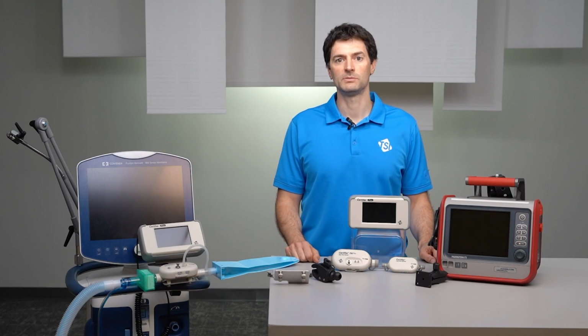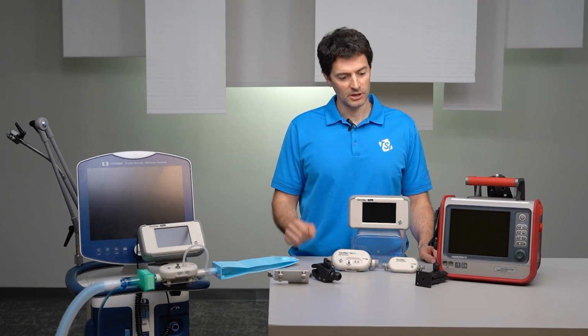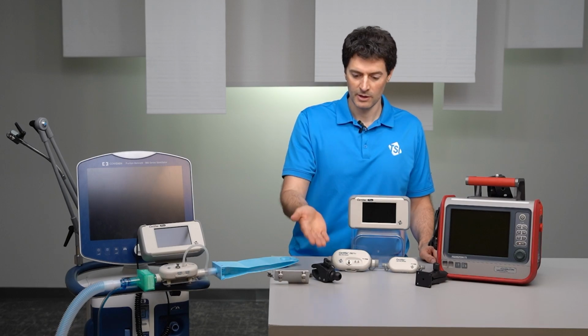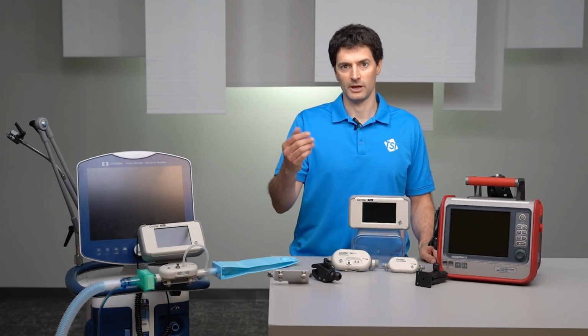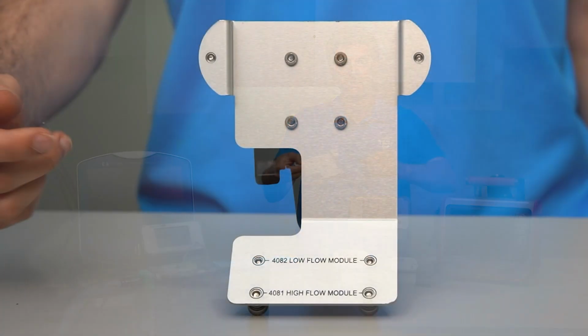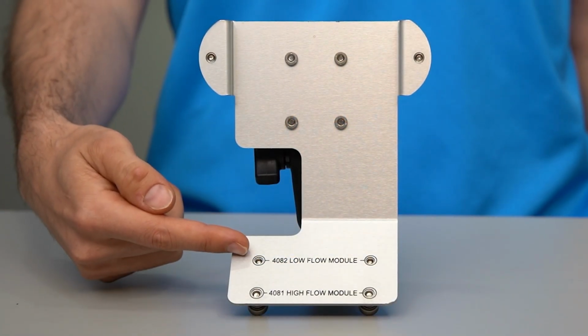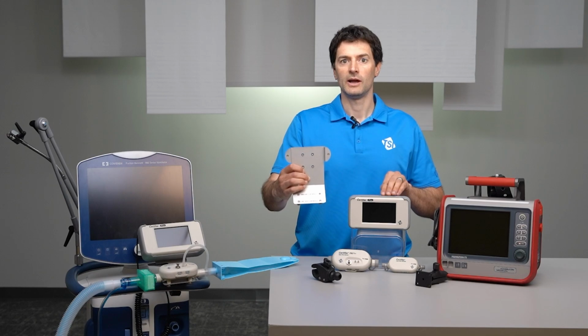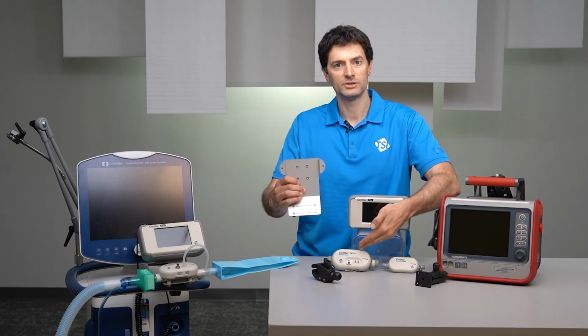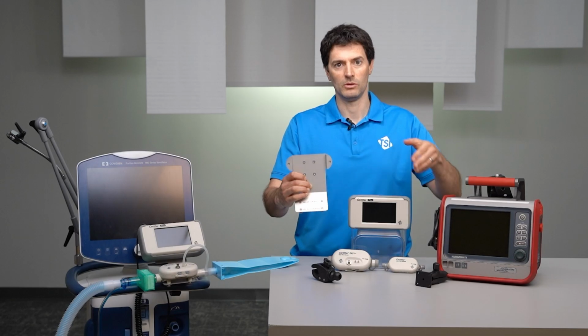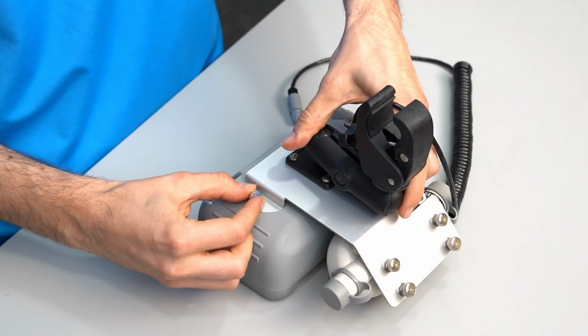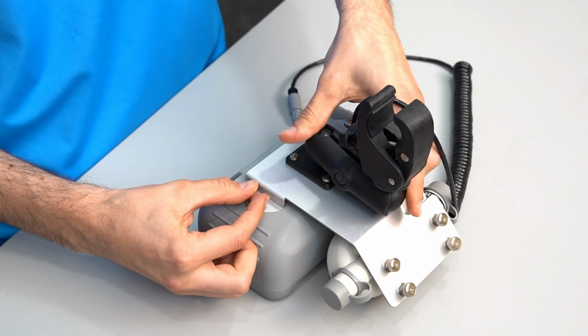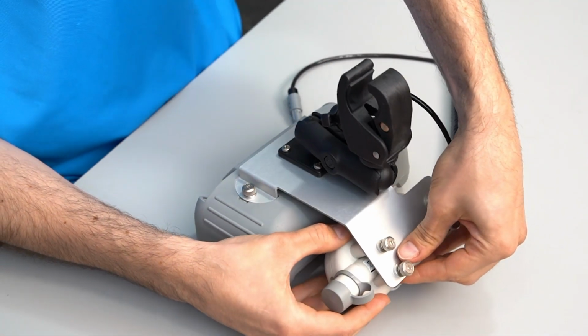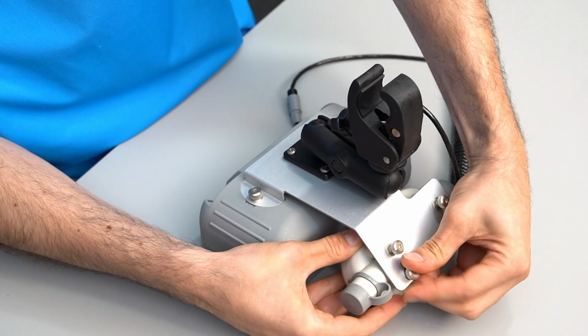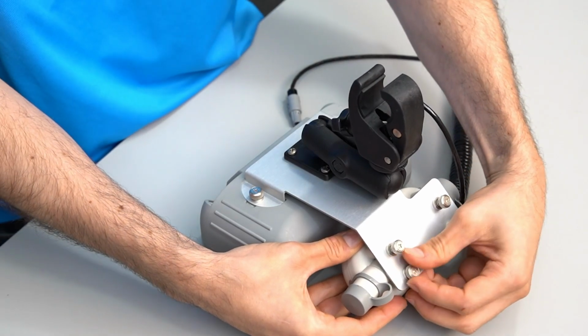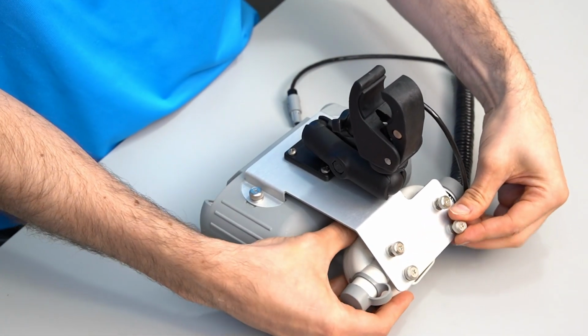The Certifier Plus mounting kit is comprised of a double socket arm, clamp, and adapter plate. The adapter plate can hold the Certifier Plus interface module and either the high flow module or low flow module. The thumb screws quickly connect the Certifier Plus interface module by hand, and because the screws are integrated into the adapter plate, this will prevent them from becoming lost.